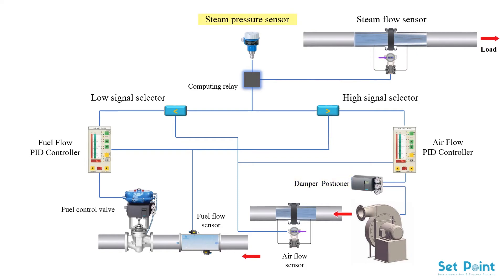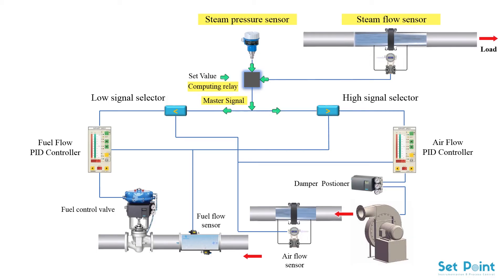The steam pressure and the flow signal are transmitted to the computing relay. The computing relay generates the master signal depending on the load of the boiler, as this master signal represents the fuel required by the boiler. The master signal is then fed as a set value to the low and high signal selectors.